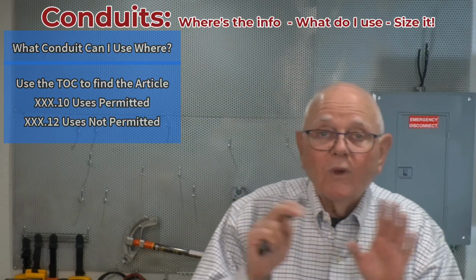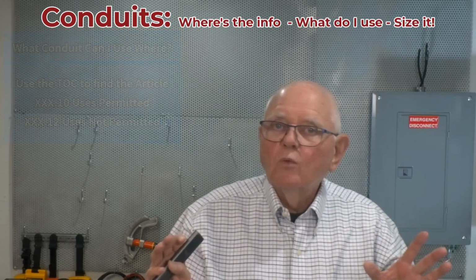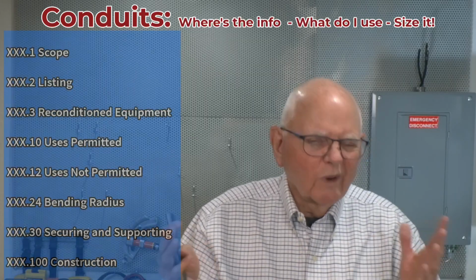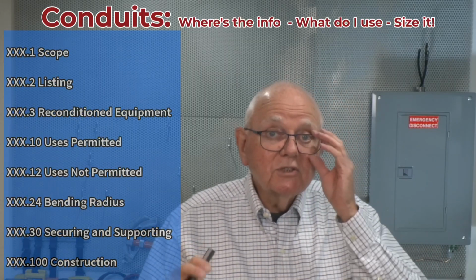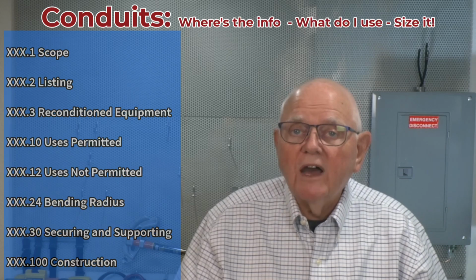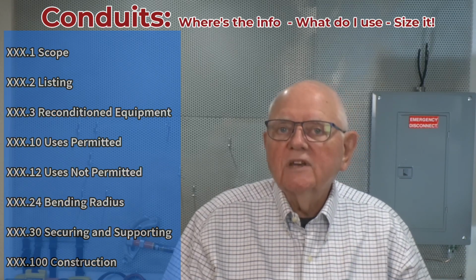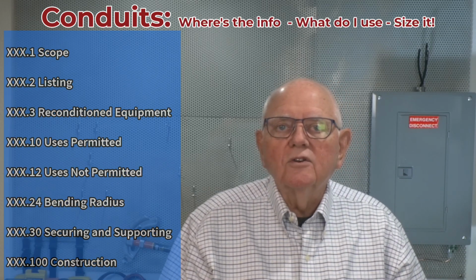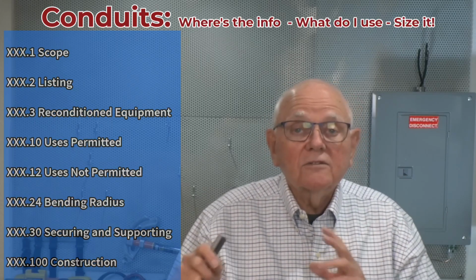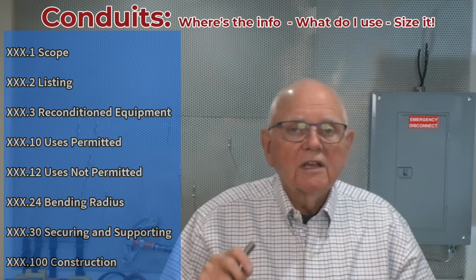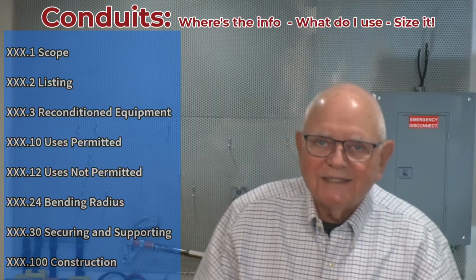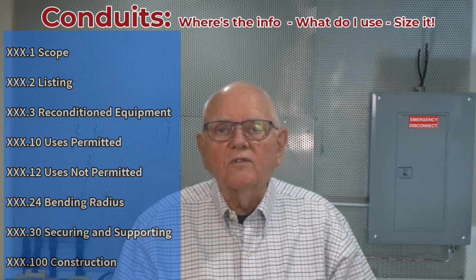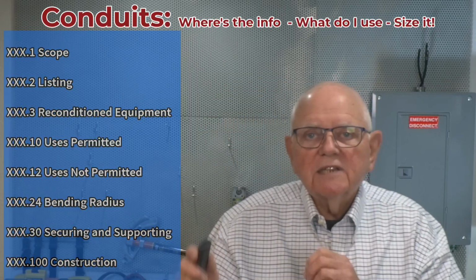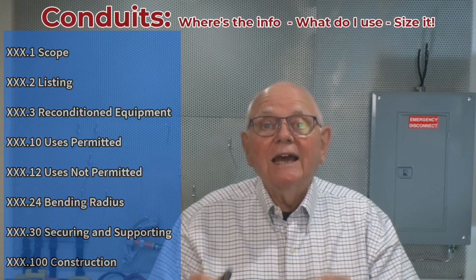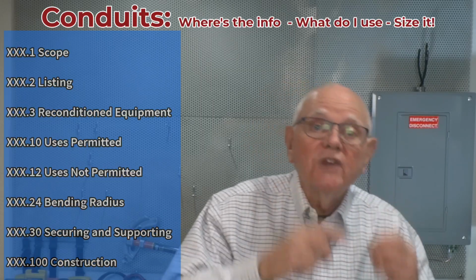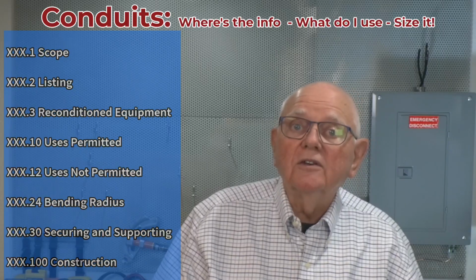The way these articles are laid out, .1 is always the scope, what the article applies to. .2 is the listing requirements. My components have to be listed when it comes to my conduits and tubing. And .3 is interesting because it talks about conditioned and reconditioned equipment. We'll take a look at that in Article 344, for example. .10, as I mentioned, is uses permitted, and .12 is uses not permitted for that particular conduit.